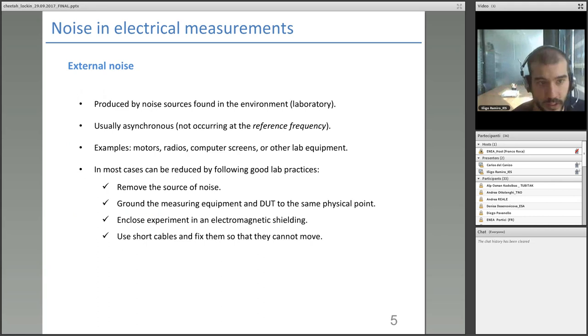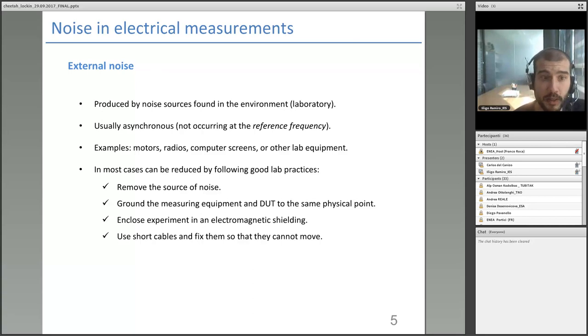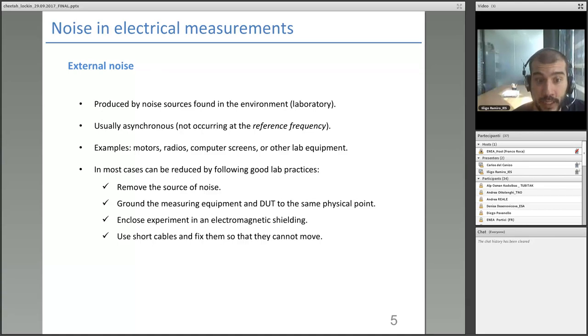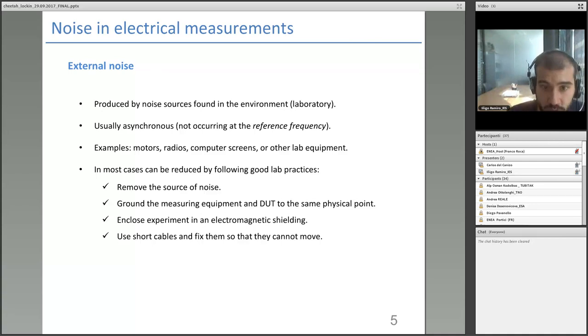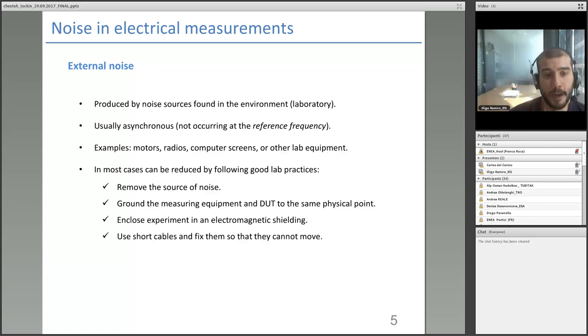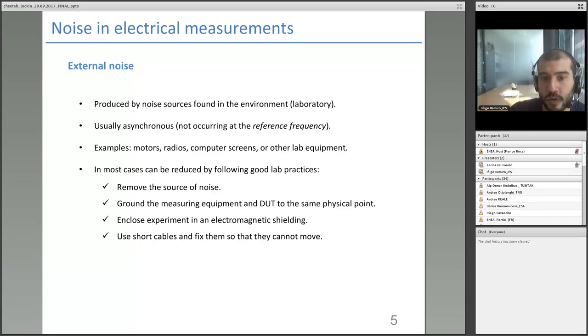Let's see what kinds of electrical noise we can encounter in our measurements. We can divide them into two types. The first is external noise, produced by noise sources found in our environment — usually the laboratory. They are mainly asynchronous, meaning they do not occur at the reference frequency. Examples include motors, radios, computer screens, or any other lab equipment. The good thing about this noise is that in most cases it can be reduced or avoided by following good lab practices.